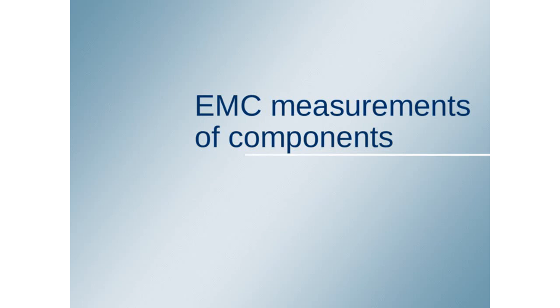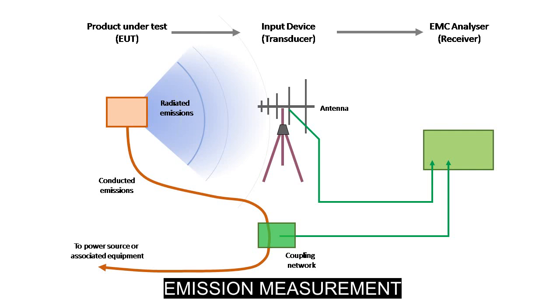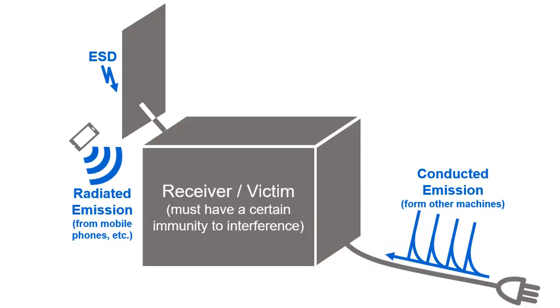Now we will discuss EMC measurements. First, we discuss emissions. Emission is every electromagnetic disturbance that is produced by the equipment under test (EUT) and given off to the environment. To guarantee the proper operation of other equipment in the vicinity, this unintended emission must be limited. Signals can generally be transmitted through air or along cables, resulting in radiated and conducted emission.